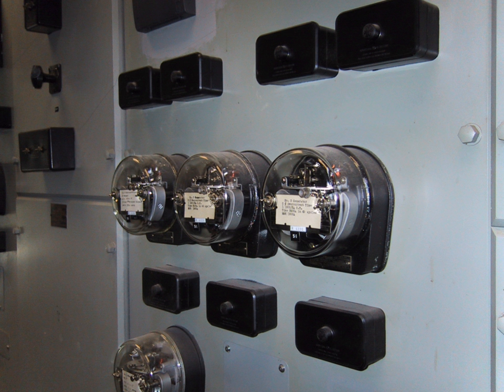This relationship of eddy currents and fluxes creates torque proportional to the input current of the primary winding, due to the two flux paths being out of phase by 90 degrees. In an overcurrent condition, a value of current will be reached that overcomes the control spring pressure on the spindle and the braking magnet, causing the metal disc to rotate towards the fixed contact. This initial movement of the disc is also held off to a critical positive value of current by small slots that are often cut into the side of the disc.